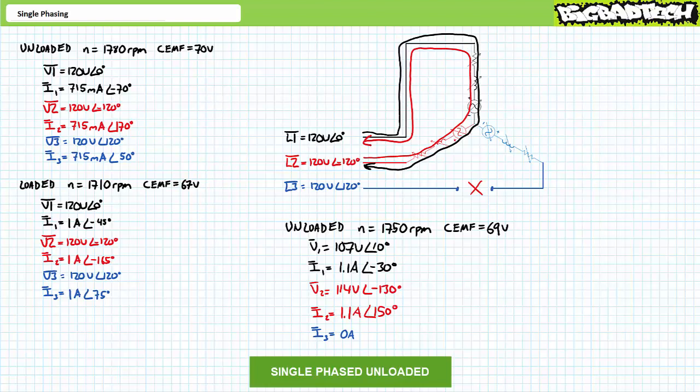Winding one experiences 107 volts at an angle of 10° and draws 1.1 amps at an angle of -30°. Winding two experiences 114 volts at an angle of -130° and draws 1.1 amps at an angle of 150°. Although no current travels through winding three, it still experiences 69 volts of counter-electromotive force while the motor is still running. This is the effect observed in the earlier hands-on demonstration — although there was a loss of connection to phase L3, winding three still experienced counter-electromotive force, just like all other windings while the motor is in operation.